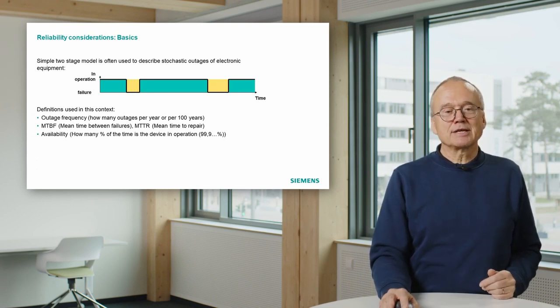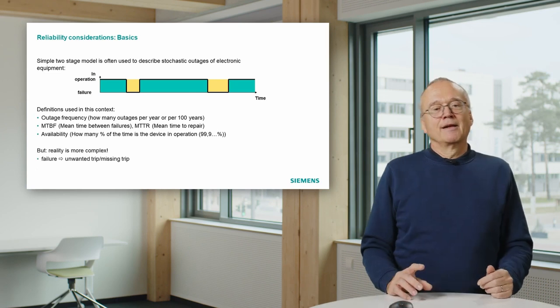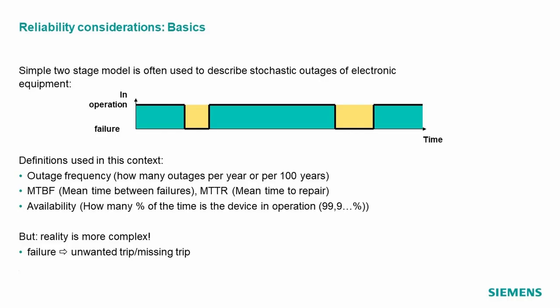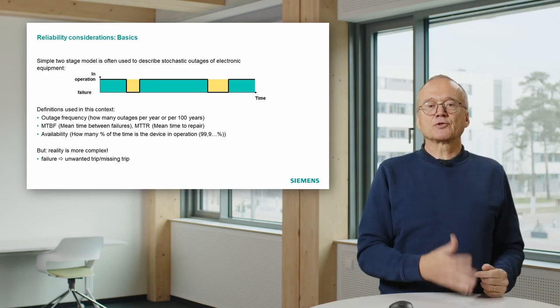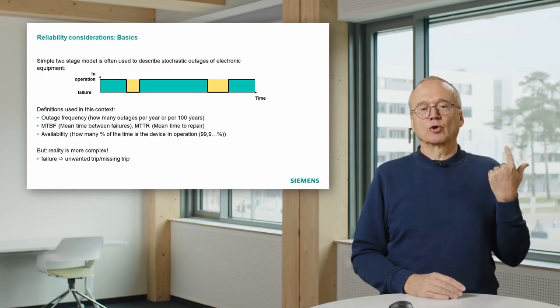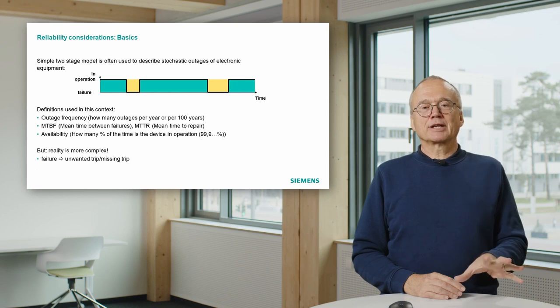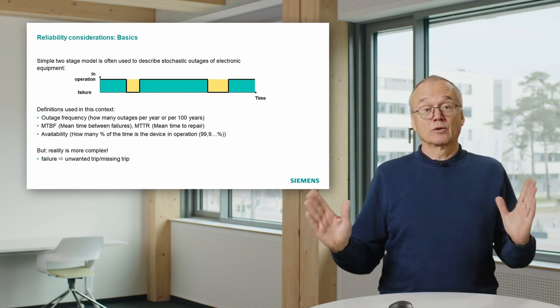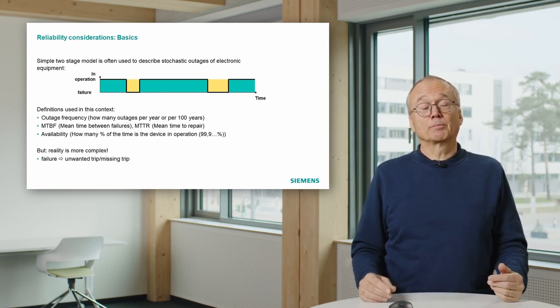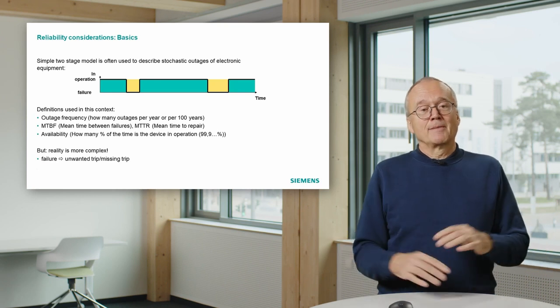reality in protection is a bit more complex. One thing is the question, what is a failure? If a relay just fails, the good thing with digital relays is if they fail, they will alarm. That means the control center knows there is something wrong in the relay, protection doesn't work, you can or you have to take the line out of operation, you replace it and it goes.